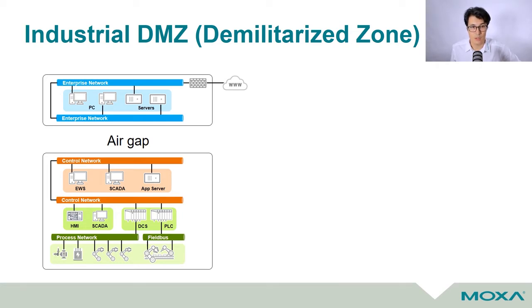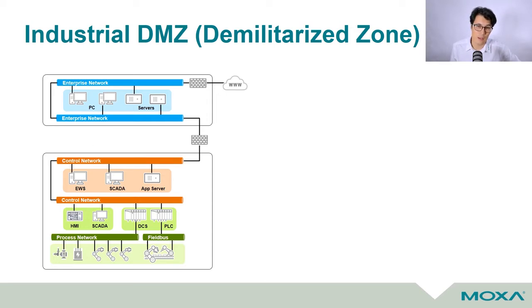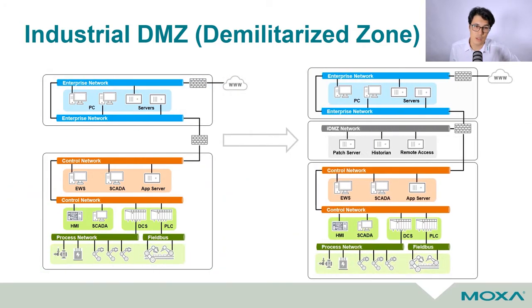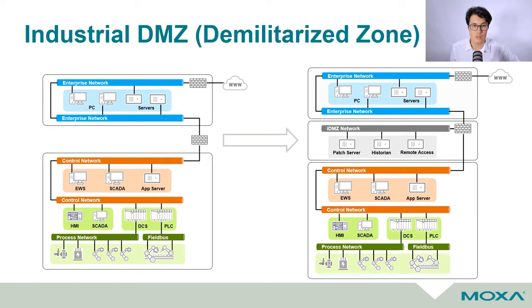Later, with the advancement of technologies and higher adoption of common IT tools in OT environments, the air gap disappeared. To manage cybersecurity risks related to the convergence of these two worlds of IT and OT, people usually installed a firewall and if they followed best practices, they created an industrial DMZ between the OT and IT networks. In simple terms, it is a dedicated area that acts like a buffer. IDMZ devices are allowed to collect information from OT applications and then share it with IT services, and no direct communication between OT and IT is allowed.